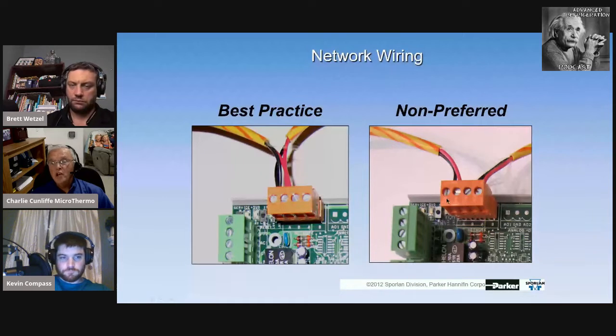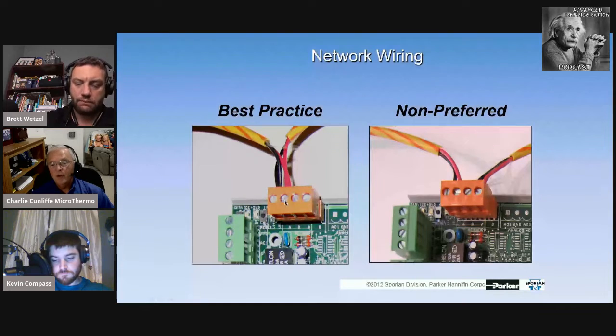We want both blacks bonded together and under the same lug, and we want both reds, or both whites, bonded together, twisted together, and under the same lug. That way, if this node gets smoked or somebody unplugs the network wire, you have not violated the network.